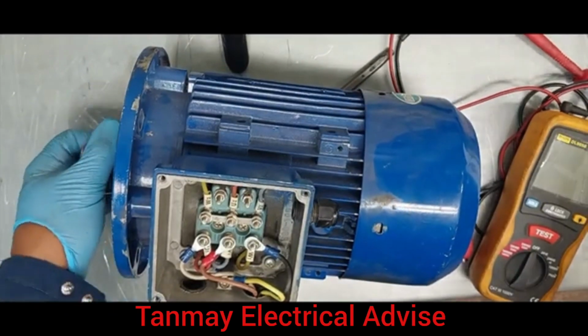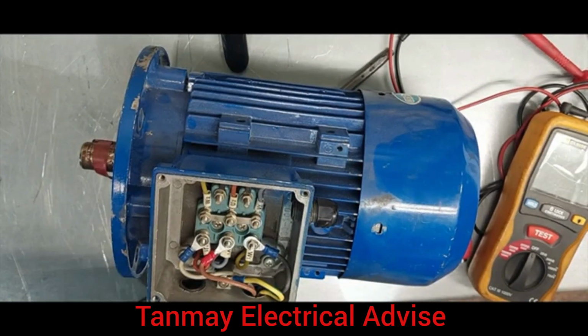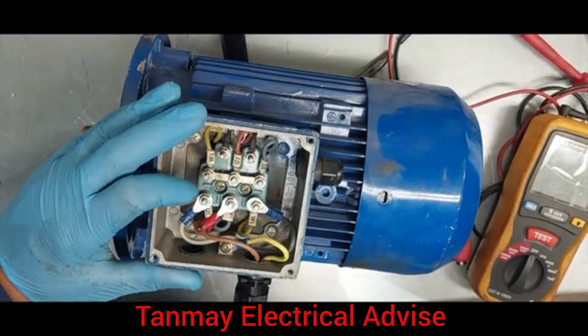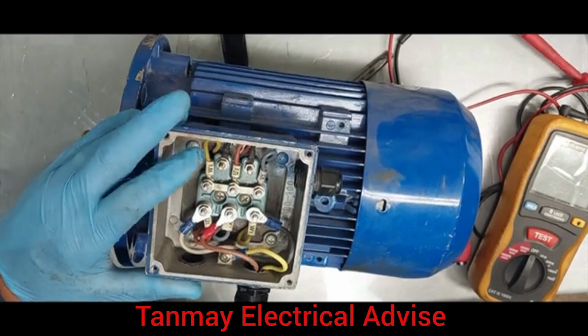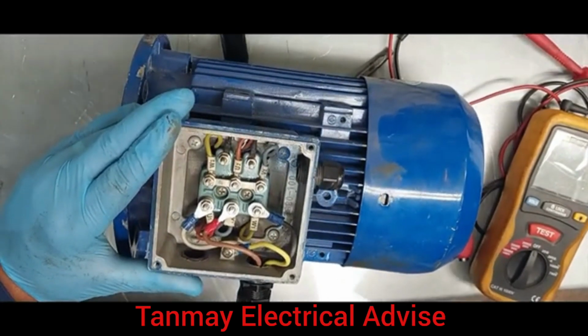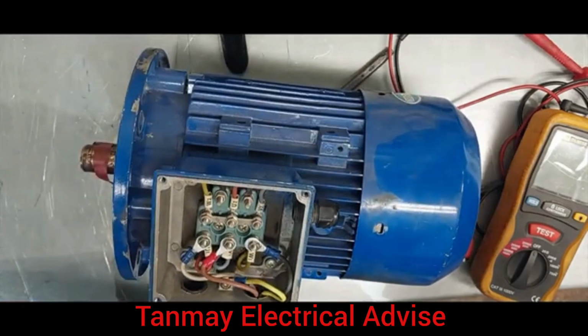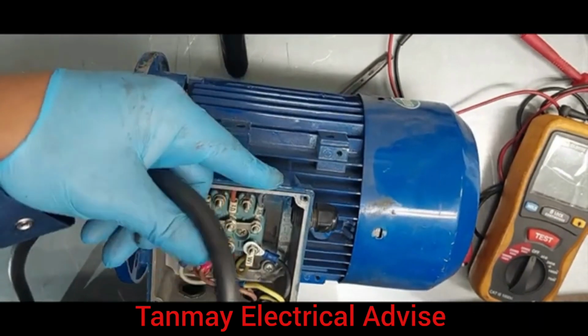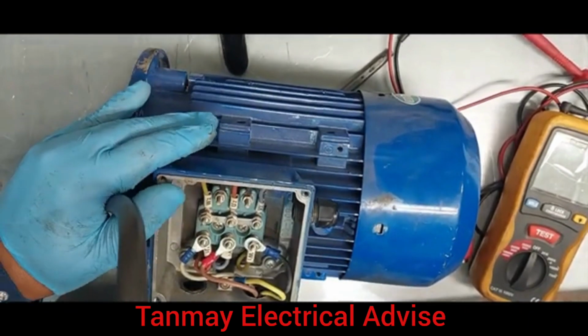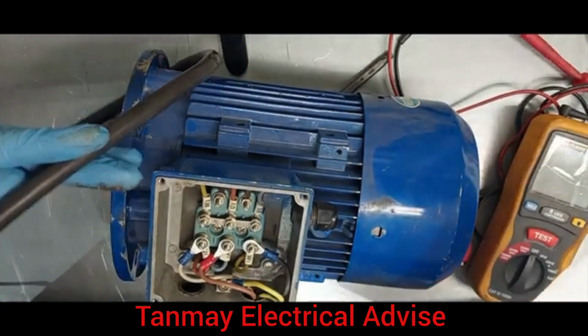One is to do a visual test. This is a quick test that we can do. We can look to see if there's burns, and we can smell it. If the motor has burned, if the winding has burned, we can smell it. And then we have to do visual observation. We have to look at the cables. We have to look for damage, if there's any damage, if there's any split.